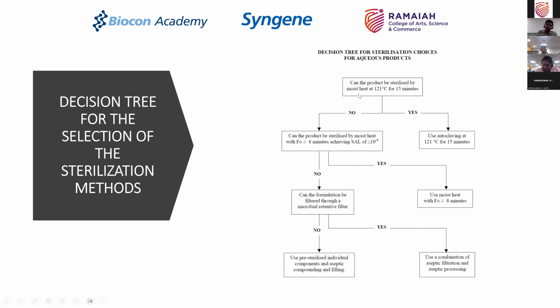But the idea is that without changing the parameters of the sterilization and keeping it at the temperature around 121 degrees centigrade, and the minimum time, if you are able to achieve a sterilization, then use terminal sterilization as the process. If not, change the conditions of moist heat sterilization so that you achieve a sterility assurance level of 10 to the power of minus 6, where FO value is greater than or equal to 8 minutes.